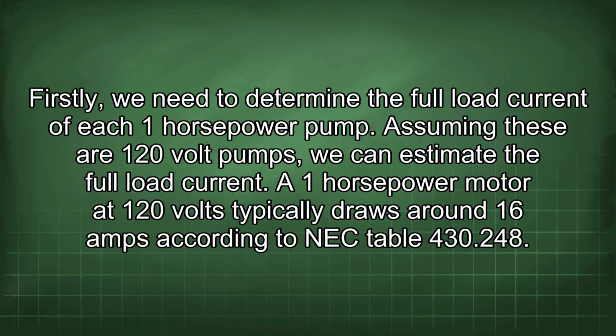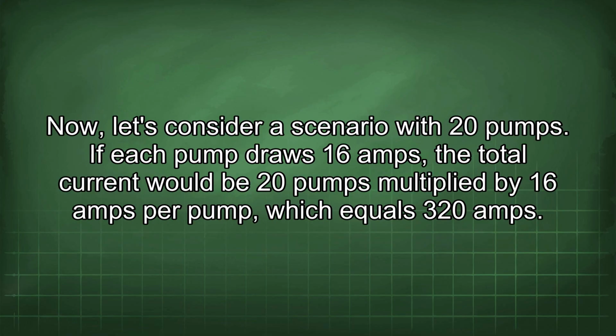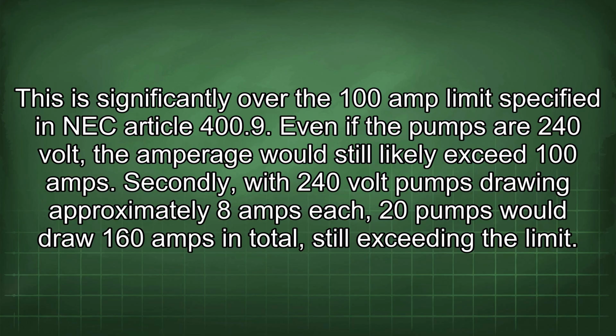Firstly, we need to determine the full load current of each 1 horsepower pump. Assuming these are 120 volt pumps, we can estimate the full load current. A 1 horsepower motor at 120 volts typically draws around 16 amps according to NEC Table 430.248. Now, let's consider a scenario with 20 pumps. If each pump draws 16 amps, the total current would be 20 pumps multiplied by 16 amps per pump, which equals 320 amps. This is significantly over the 100 amp limit specified in NEC Article 400.9.